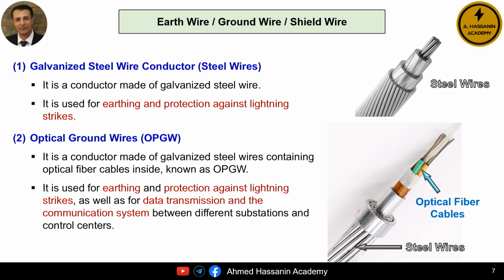Now, what is the importance or function of the second type, which is the optical ground wire, OPGW? Of course, its primary function is grounding and protection from lightning strikes because it contains steel wires. The second function, which distinguishes it from the traditional earth conductors, is the transmission of information and the communication system between different substations and control centers because it contains an optical fiber cable.